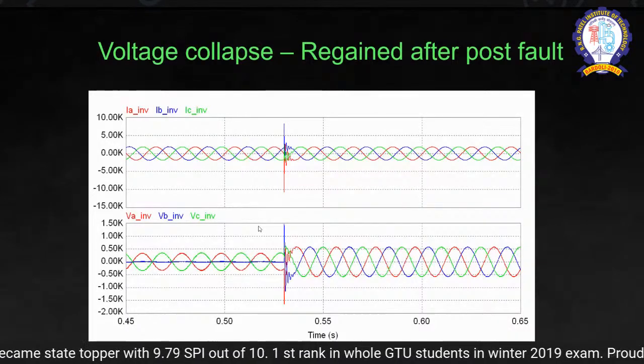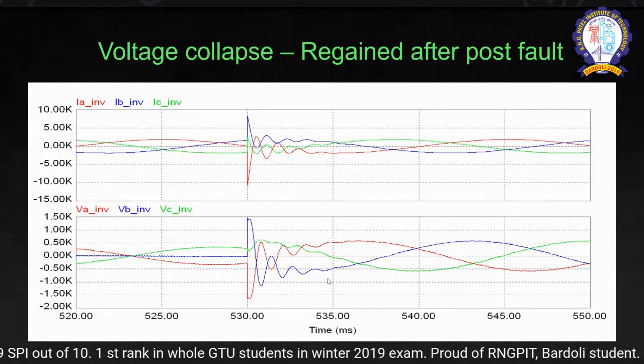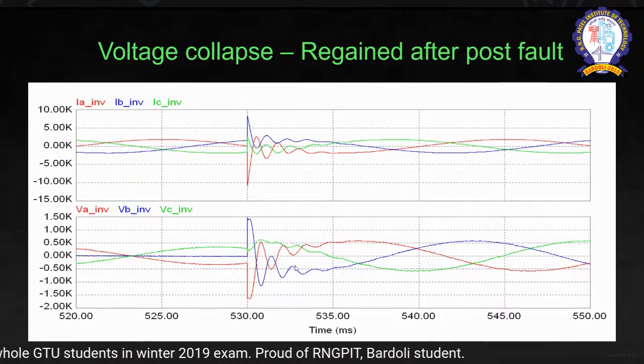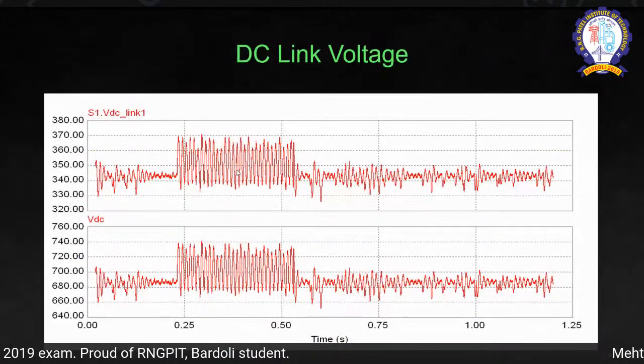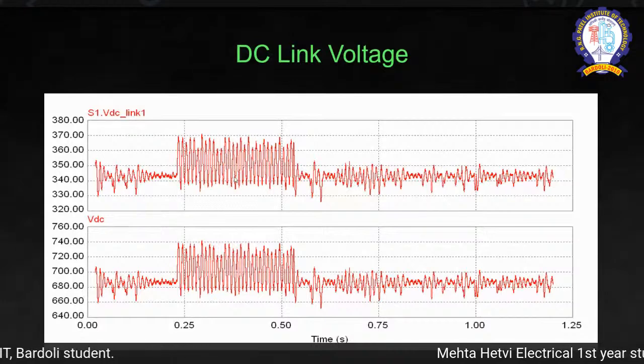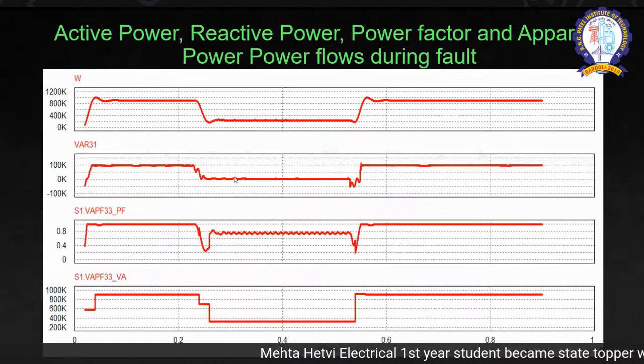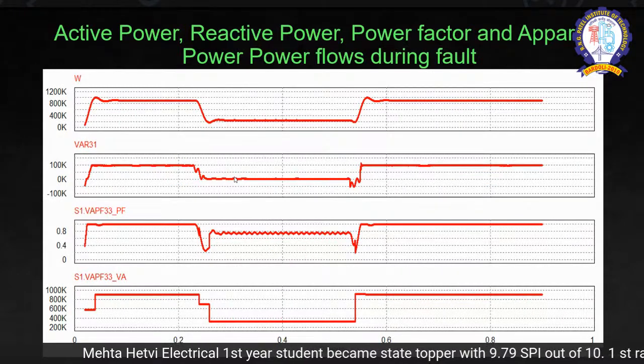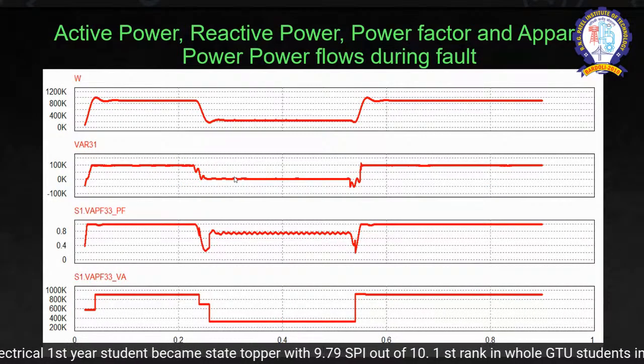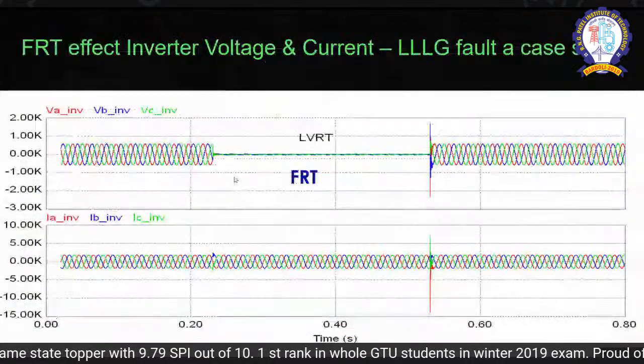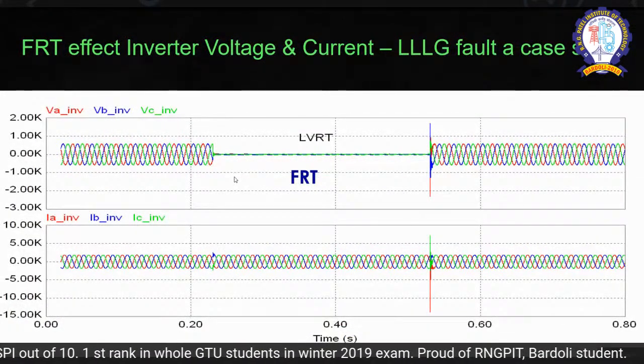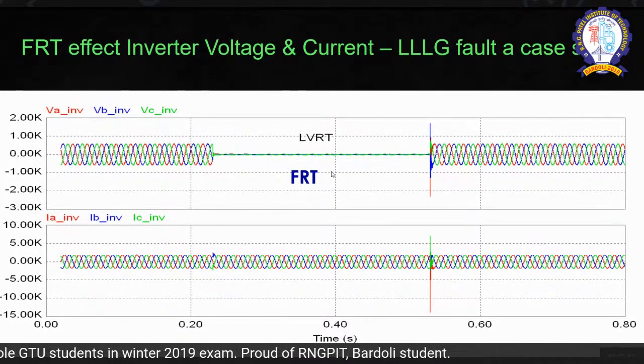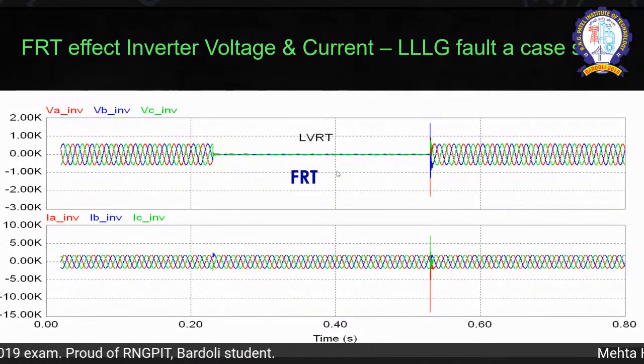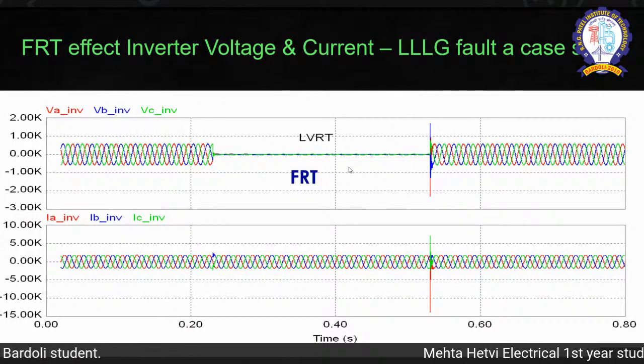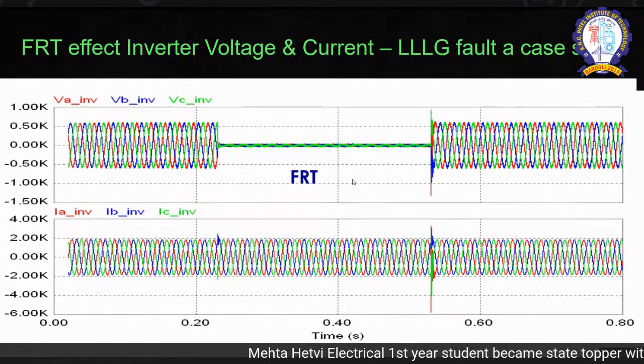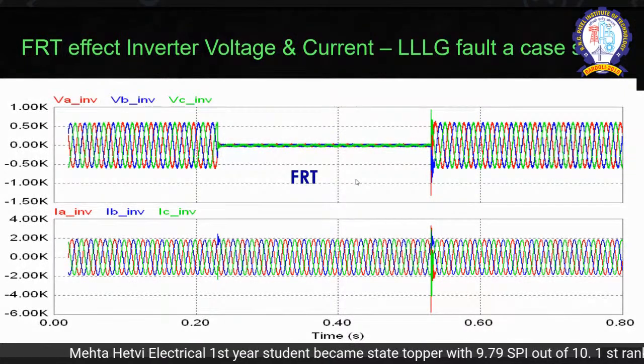Now, if you zoom in, it is still less than the tripping time of the relay. So again, the relay will not trip over here. And this is the rise in DC link voltage during fault time. And these are the active and reactive power flows at the fault time and the VA capacity of the machine. Now, in case of a triple LG fault, this is the LVRT. This is the exact demonstration through simulations of the low voltage ride through. And this is the zoomed view of FRT.